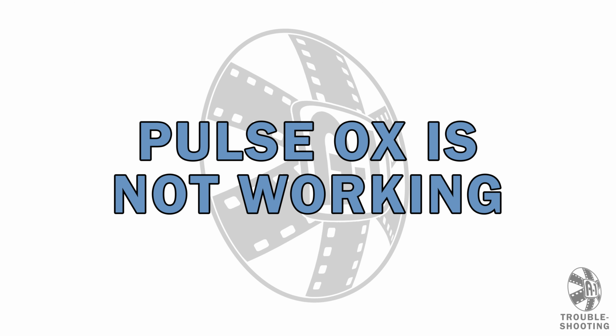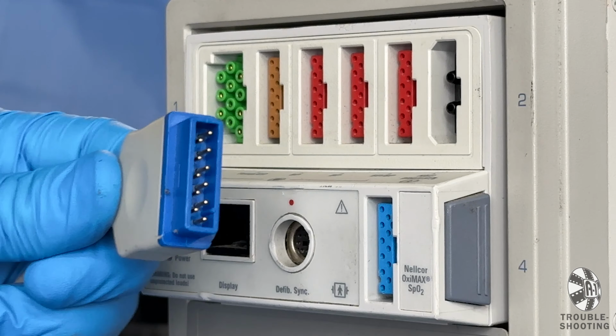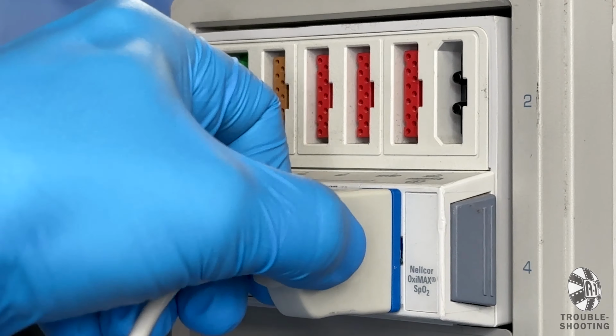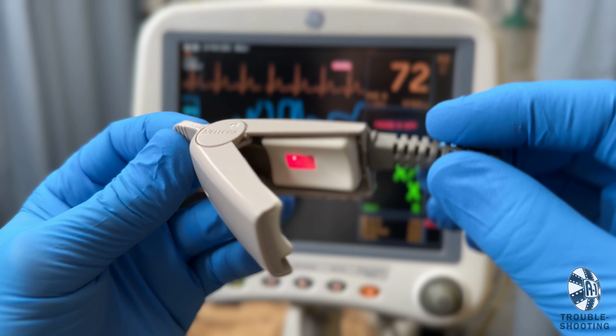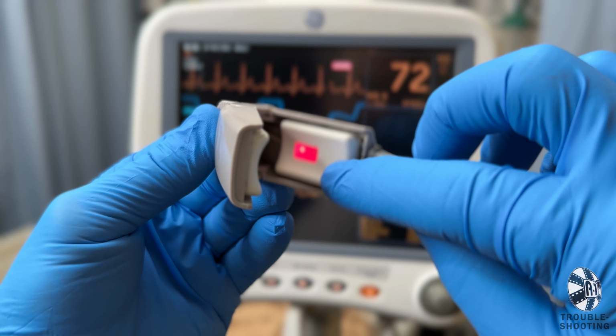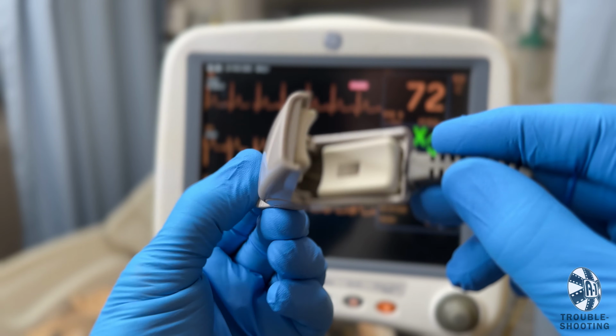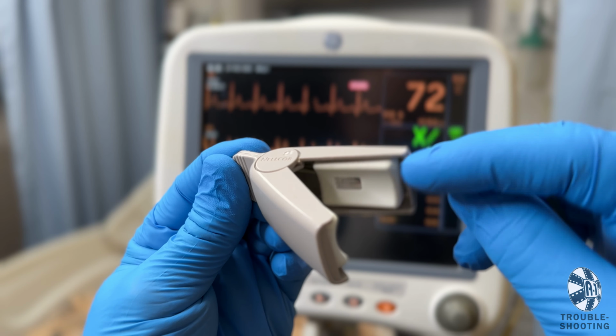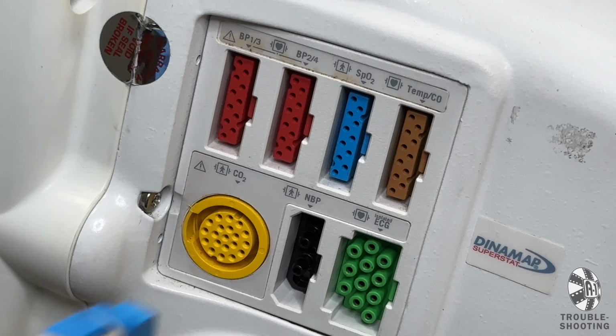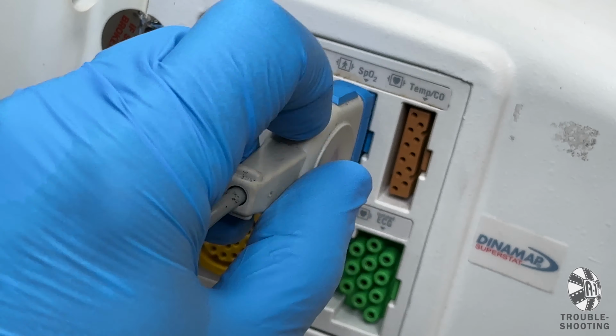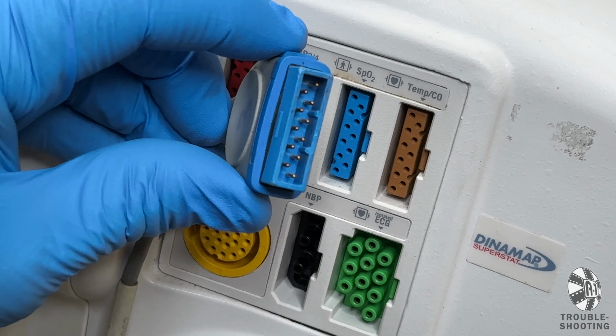Pulse ox cable is not working. After plugging the blue-ended cable into the blue port, check to see if the finger probe is lit red inside. If not, it is possible the finger probe was damaged and you will need a replacement. It is also possible that the cable input is mismatched to the port.